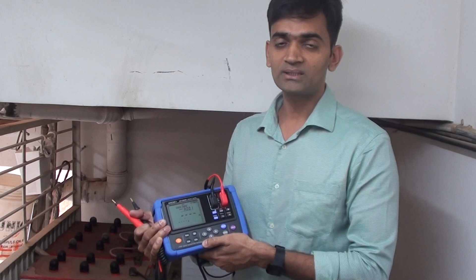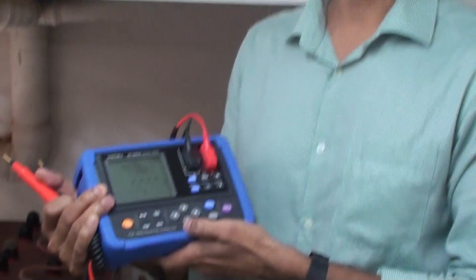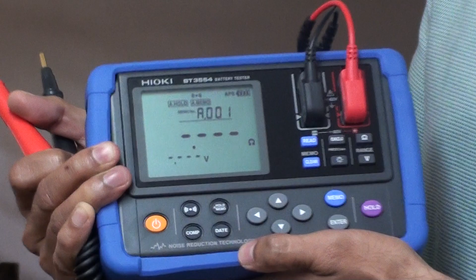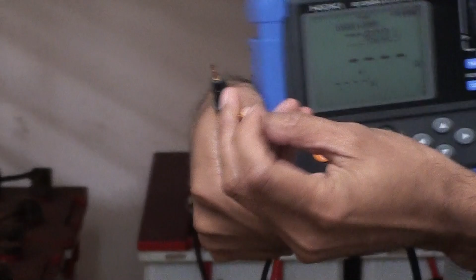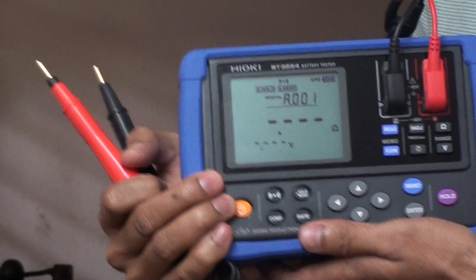That will give you a 3 milliohm to 3 ohm range for the resistance. At the same time it will give a voltage range of 6 volt to 60 volt. So here, while testing the battery, everyone uses the four probe principle method. In this Hioki battery tester, there is a tip pin, so it works on the 4-wire principle method. Once you touch this battery tester, it will pass some AC millivolt to the battery. At the other end it will sense the voltage. Whatever the difference between the voltage, that particular voltage and resistance will show on the display. That means we are getting the actual resistance of the battery.